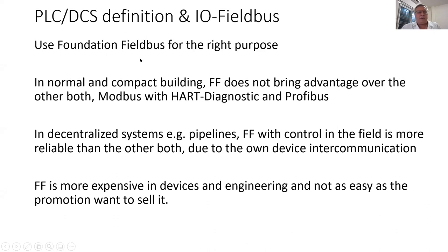It does not mean that Foundation Fieldbus is a bad bus, but you should look at where you use it. Let's say in decentralized systems like pipelines, or where things are very far apart, then it might be good to have Foundation Fieldbus. But you can do everything also with the other buses, with Modbus and Profibus connections. Modbus comes in two different forms: Modbus RTU, which is serial like Profibus, and also Modbus over Ethernet. Then we use specific Ethernet devices to extend to a longer cable. With Modbus and Profibus, we talk about a maximum cable length of roughly 1 kilometer, and that should be long enough for every normal plant in a building. So there is no reason to go for Foundation Fieldbus because of cable length or whatever.